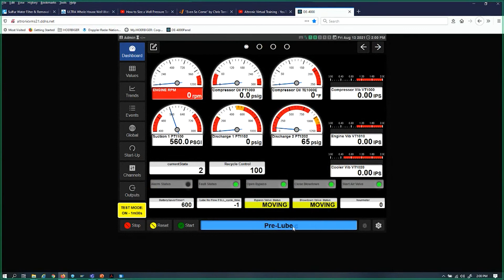So it goes into a warning state and a pre-lube state. On this particular one, the first thing it's looking for is a permissive. Permissive A, I happen to know, in the pre-lube state, is that oil pressure has to be above 10 pounds. So I can click 55 since that's where I want it operating anyway. While waiting for the pre-lube to finish, I can give it some oil temperature, 180, and maybe compressor vibration, I'll give it a 0.5.